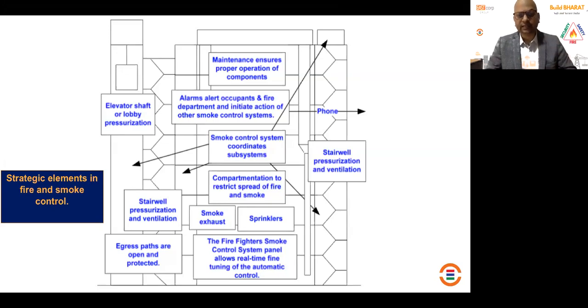Consider the most critical area, the stairwell. Stairwell pressurization means creating a positive head pressure in the stairwell, higher than the lobby area. You create that differentiation. In India, the required difference is 50 Pascal. That means in the staircase you inject pressure up to 80 Pascal, while the adjoining lobby area operates at 50 Pascal... sorry, 30 Pascal, giving a 50 Pascal difference in your stairwell pressurization.